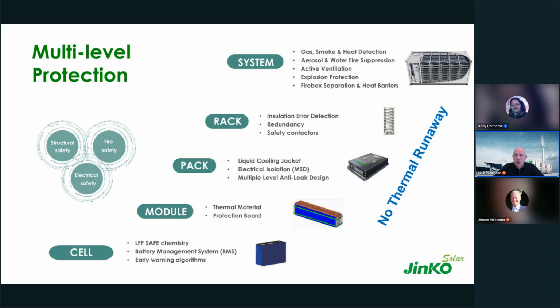the scalability of that. So in terms of the system, fully integrated gas, smoke and heat detection systems, we've got fire suppression systems. If everything else goes wrong, we've got active ventilation, and we have explosion-proof deflagration systems, and also something that is not very common. We also have separation at all levels within the system. We separate the areas and we call them fireboxes. Okay, so if something was to go wrong, if there was a faulty cell, or if a forklift was to drive through the side of your container and set the fire, let's face it, you can make anything burn, you can make anything explode if you try hard enough. So we want to mitigate that by having separation, which means that it's extremely unlikely that you would see a fire outside of a specific area.